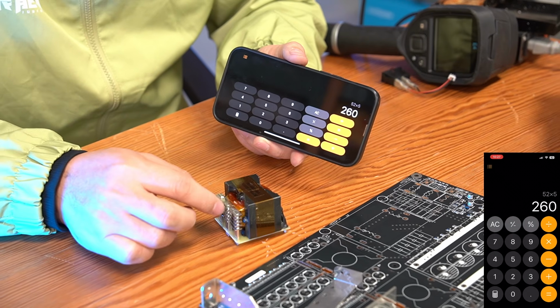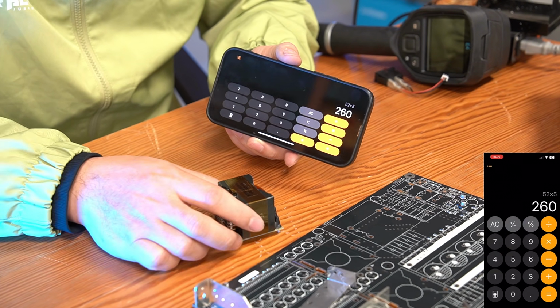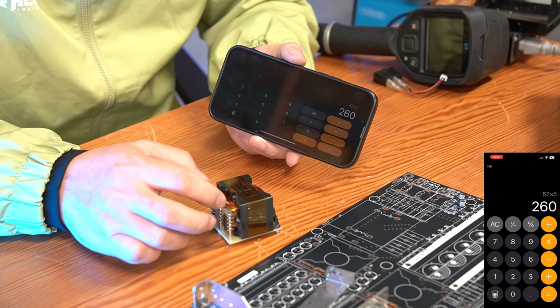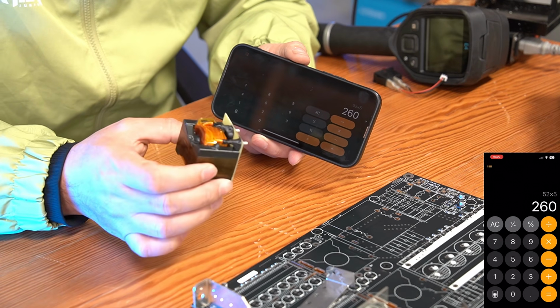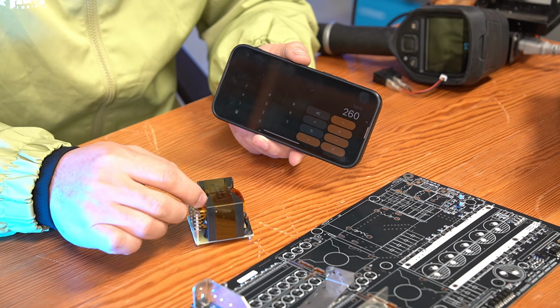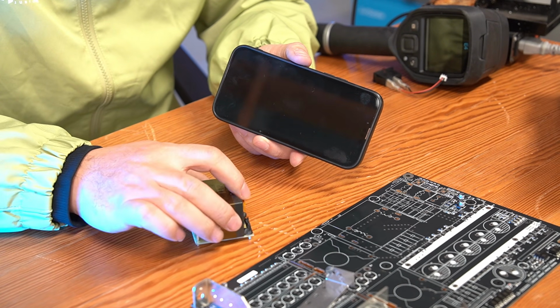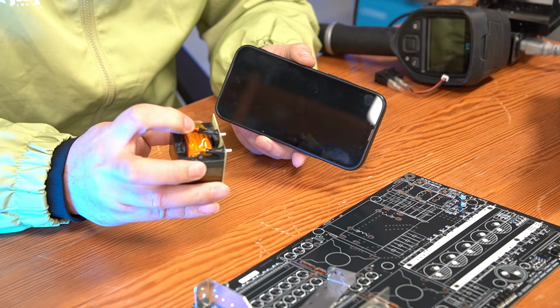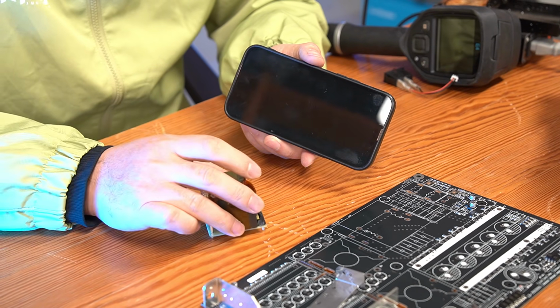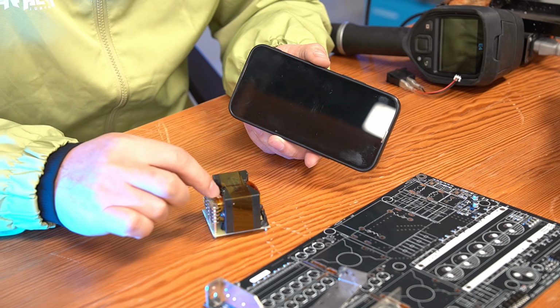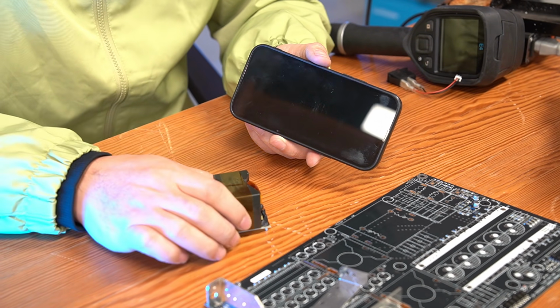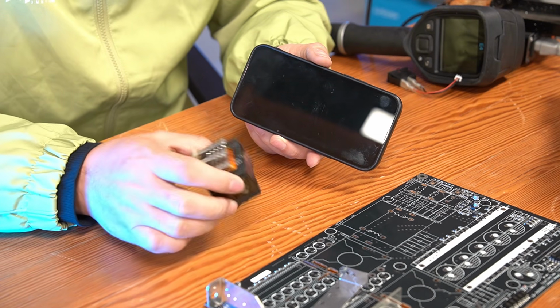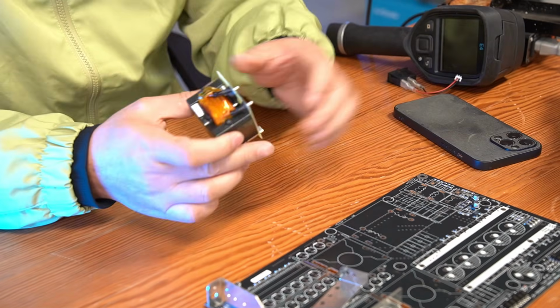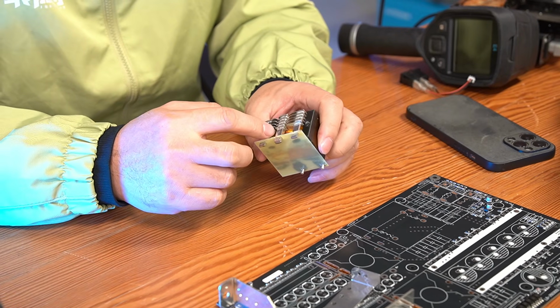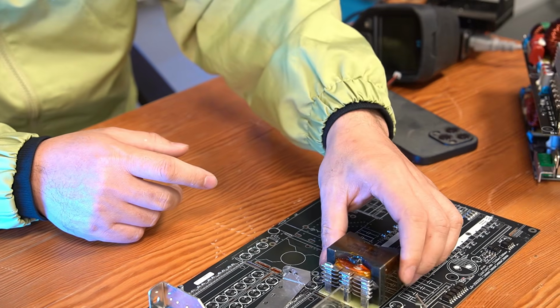This primary coil is guaranteed not to exceed 120 degrees Celsius. The insulation material wrapped around it can withstand temperatures as high as 180 degrees Celsius. All the materials used here are high quality, high temperature insulation sheets. In our 12 volt 3080 watt unit under full load, each transformer only carries 130 amperes of current, which is half of the design capacity, providing a 100% safety margin.